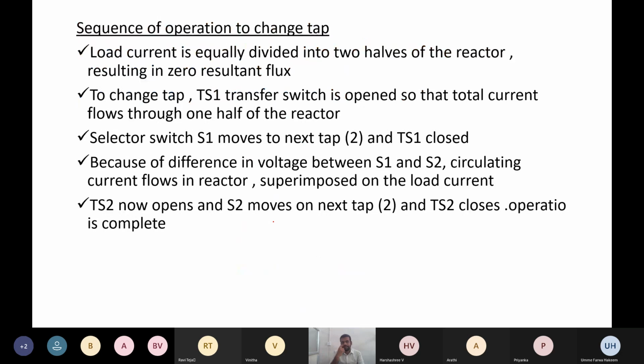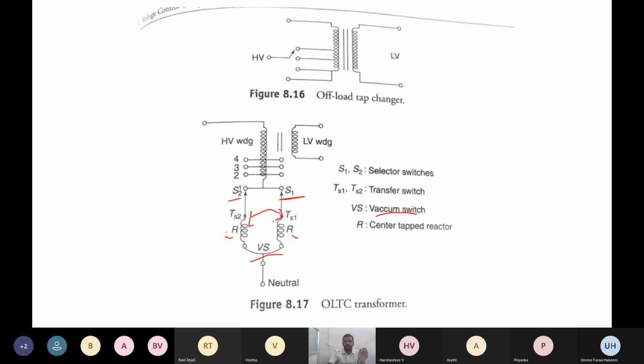Okay. So the next is the procedure. So how actually the tap position should be changed. So that is the sequence of operation to change the tap. Okay. First step. What is the first step? Load current is equally divided into two halves of the reactor, resulting in a zero resultant flux. So here we are having two reactors. So this is reactor 1 and this is reactor 2. So in these two reactors, the load current that is actually flowing should be equally divided. So equally divided. So that is the first step in order to change the taps.